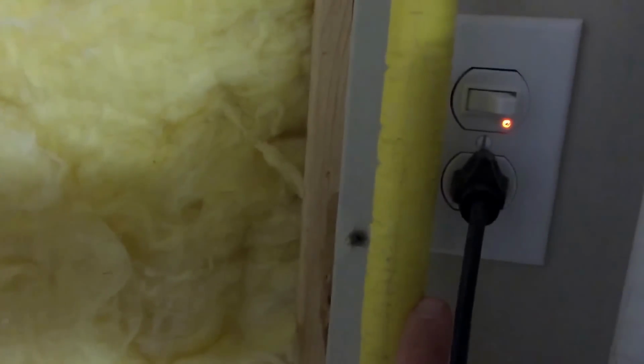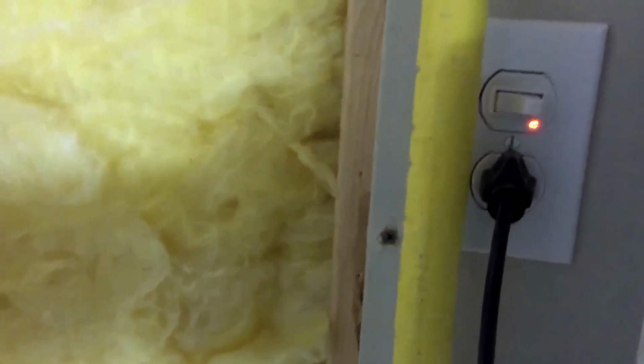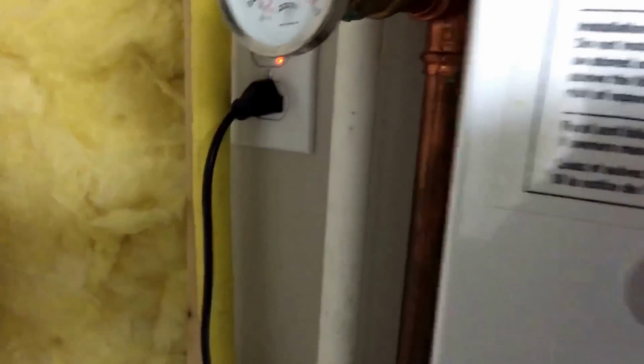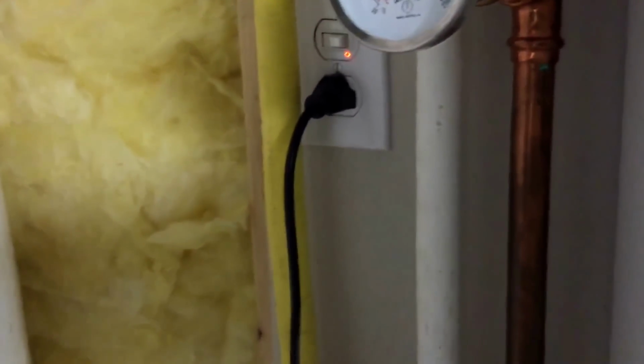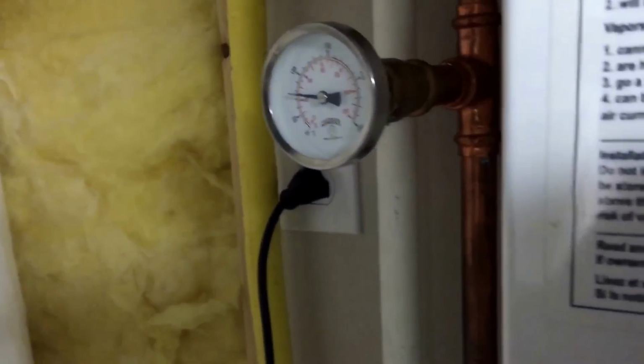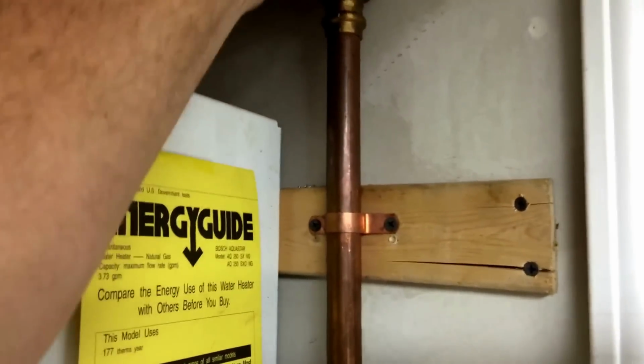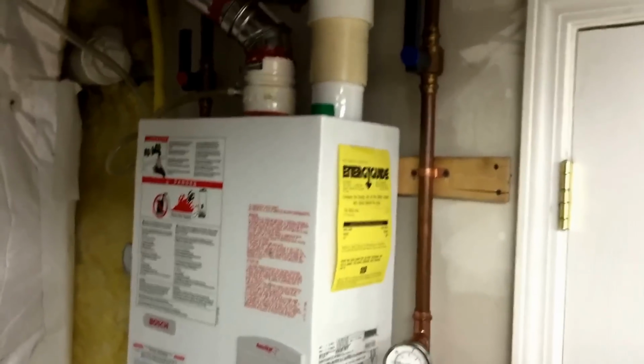Shut off switch at the hot water heater. This is a plug-in type of tankless water heater. I mean, there is a shut off switch here too, but, redundant, you can have a shut off switch for your main connection. Also notice there's shut off valves. That's another thing I find a lot on boilers and things like that, where there's no valves anywhere to do anything. If they just put a couple extra valves in, you could actually service the equipment correctly.